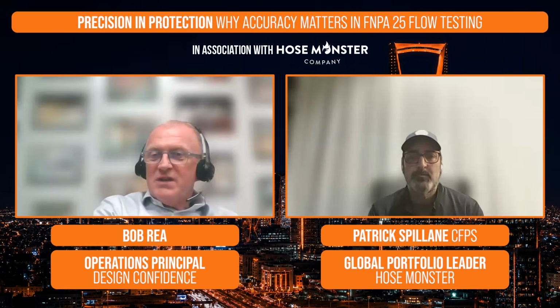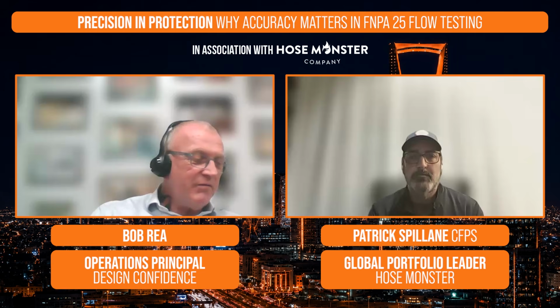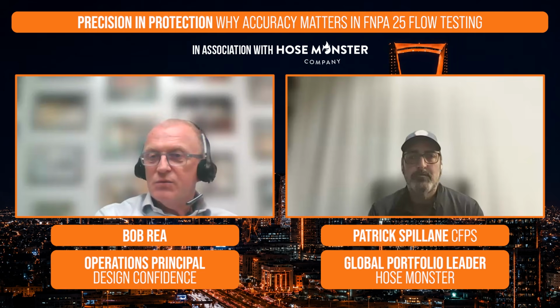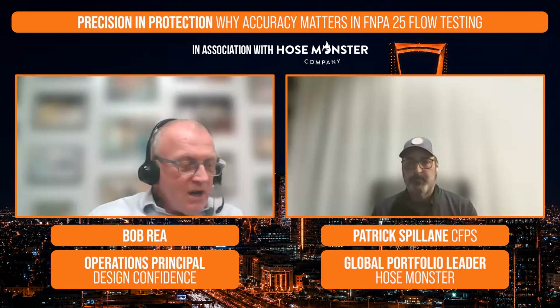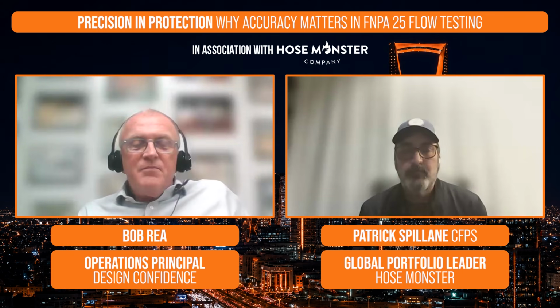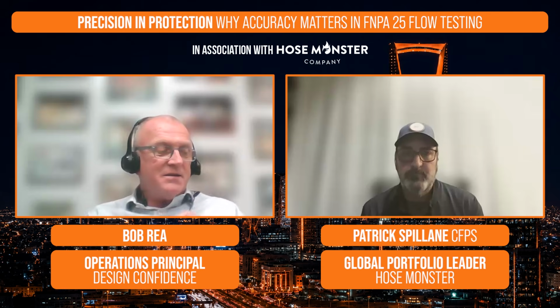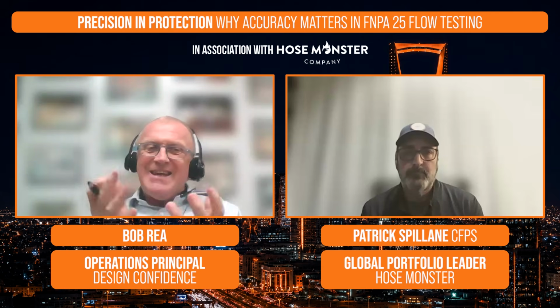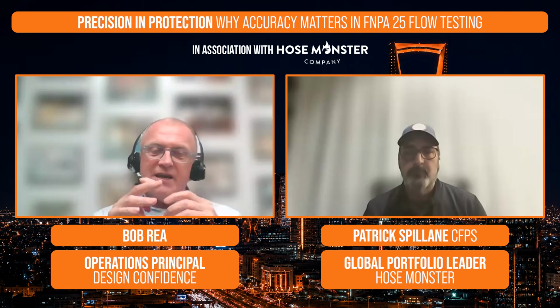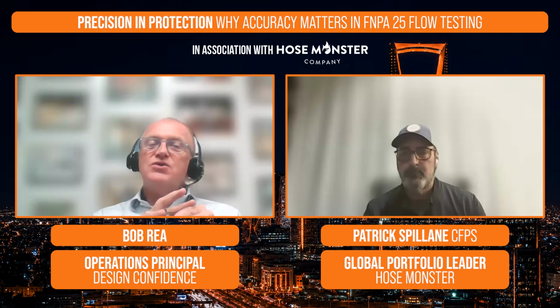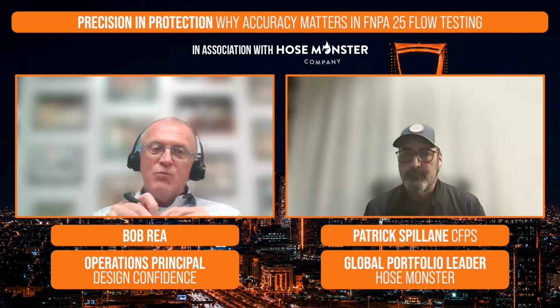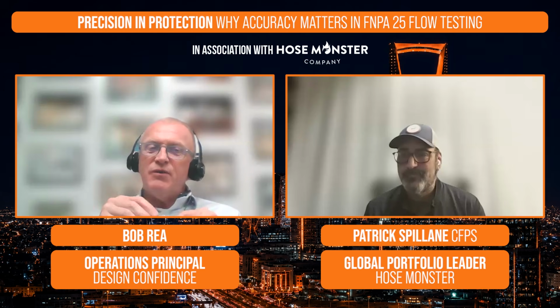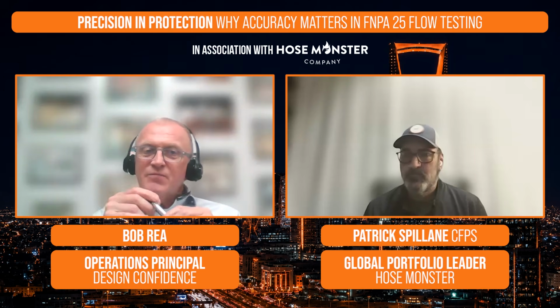So we did have one question that came in from Abdullah, which I will read to you. And then I'll come back to one that Nafis spoke of as well. And Abdullah asks, in a hospital fire pump test, churn test, what readings or what indicators would cause you concern, and what should he look for to try and give an indicator the pump may not provide the water in the case of a real fire?